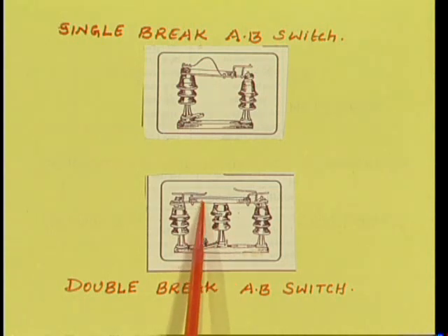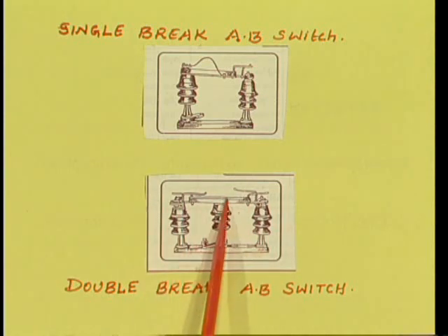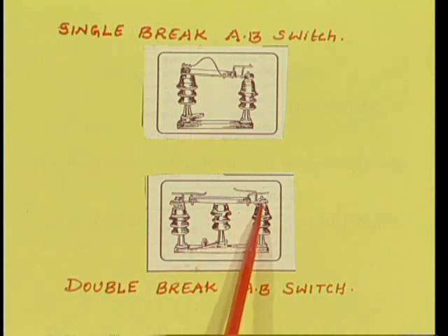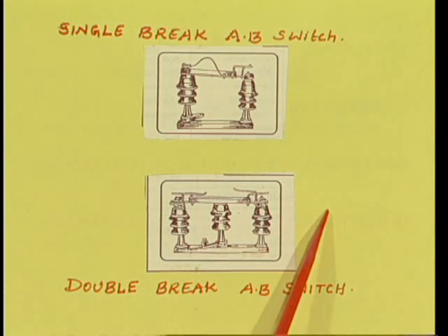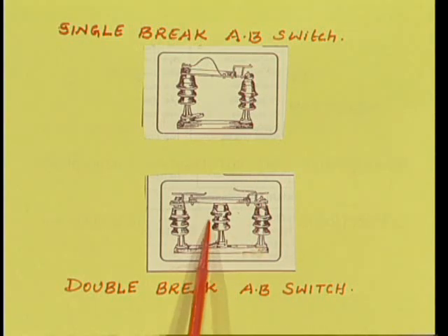Therefore the connecting rod or operating rod connects between the two insulators on either side, and supply will be taken from either end of the insulators. So using this insulator, we can take two supplies, one supply from here and another supply from here. So we can take one supply, as well as both the supplies, by operating the center break type of air break switches.